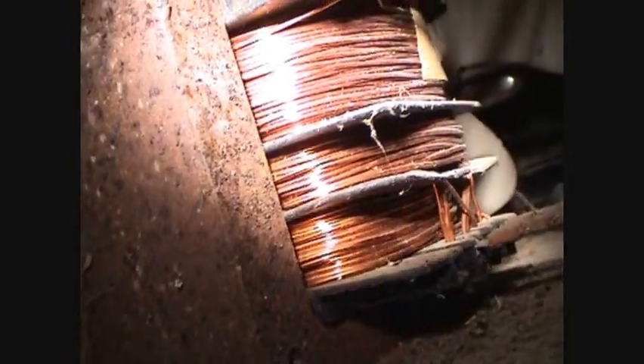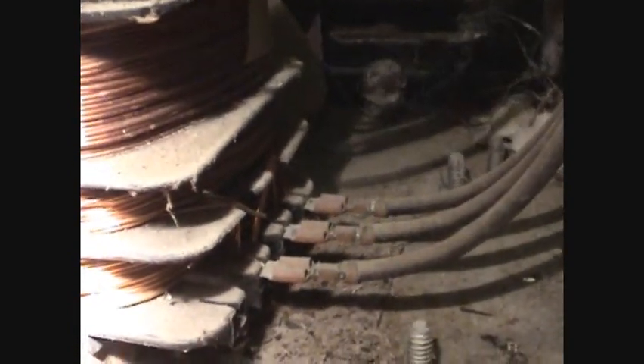I believe that the top winding is the primary, and it looks like it's got two sets of secondary windings. It's kind of hard to get all this in the frame. Those secondary windings are ganged together on those three bottom connections, which basically form a common, and they go to an inductive type ammeter. That's how it's measuring the current.